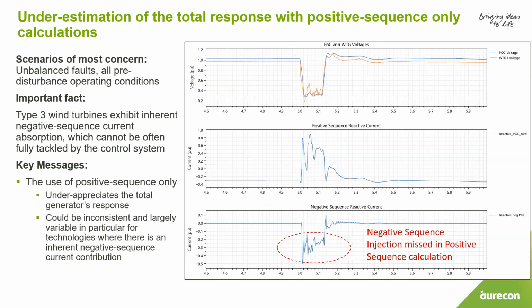The third issue I wanted to raise, again for a similar two-phase to ground fault: in this case the response doesn't go negative. It definitely follows a positive trend in the middle graph, which is the positive sequence response. But then we plotted the negative sequence response, which is the bottom graph, and you can see that in this case it goes negative and stays negative. Again, it might give the impression that this is an unexpected or unacceptable response, because a fault happened and you expect it to go upwards. It's not an over voltage, and the response clearly goes downward as far as negative sequence current is concerned. But what is happening exactly?